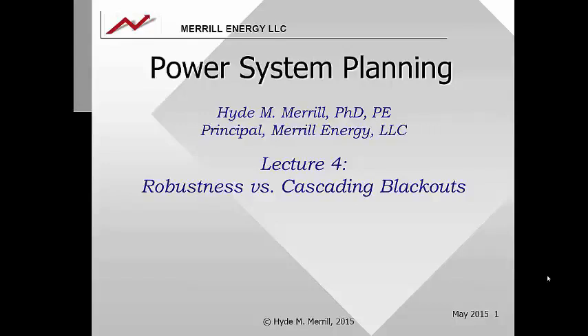Shortly after noon, voltages were depressed in the Cleveland area. The operator of the East Lake 5 generating unit tried to correct this by increasing the reactive power of his unit. Unfortunately, he asked his generator for more than it could provide, so automatic equipment took it out of service to protect it, and it remained out of service for the rest of the afternoon.